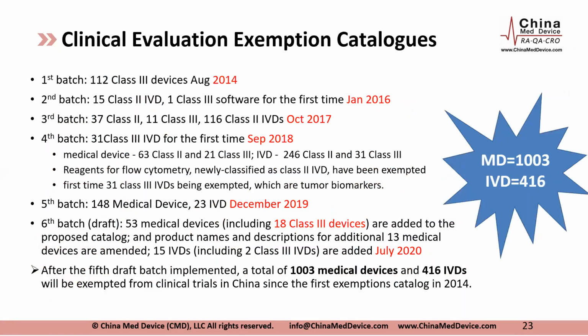And then this is an important catalog started in 2014. It is updated each year, and you can contribute. If you're not on it, that means you have to do clinical evaluation through different pathways. But the important thing you can contribute is, if you're not on it, try to submit why you should be on it, and maybe next time you'll be included. If you don't raise your hand to NMPA to submit that yours should be evaluated, they have a centralized group to evaluate this and add products each year.